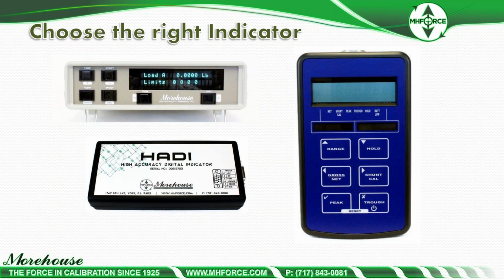So I think last week we talked about choosing the right load cell. I want to talk a little bit about choosing the right indicator. Here's a 4215. This has a display. It can go millivolts, pounds, kilonewtons, and can be set up in whatever unit. That's this one right here at the top. Then we have our HADI. This is probably my favorite indicator, a high accuracy digital indicator, less expensive than the 4215, a true 6-wire system, which we'll talk about later, and all around just really good filtering, really good meter.